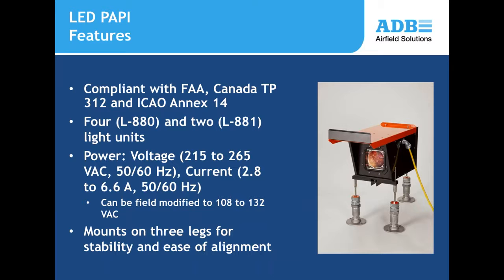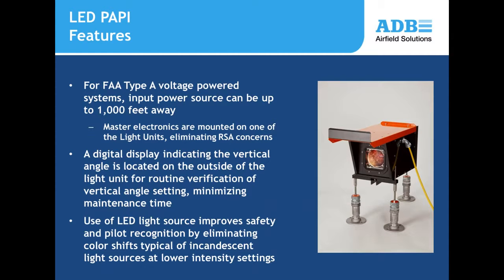The ADB LED PAPI mounts on a three-leg design for greater stability. One of the key advantages in the FAA market is that input voltage is fed directly to the first light unit in the string of two or four. Traditional PAPI designs required a separate voltage master box mounted to the rear or side of the units. The FAA is increasingly restrictive about devices in the runway safety area, so eliminating that box is a significant benefit of the LED PAPI design.